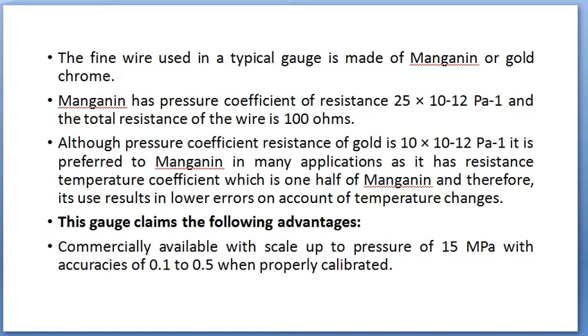So gold is actually preferred, because its resistance temperature coefficient is half of Manganin, and therefore its use results in lower errors due to temperature changes. When temperature changes, its resistance changes only half as much, which is why it is preferred.